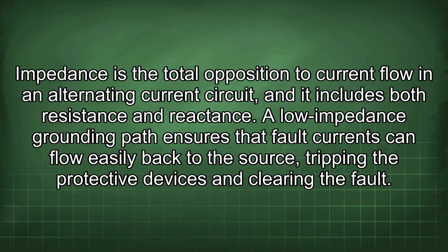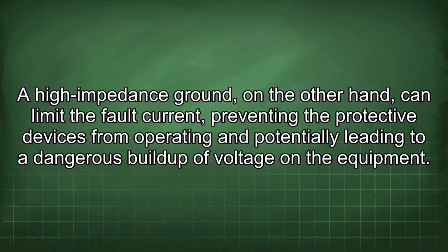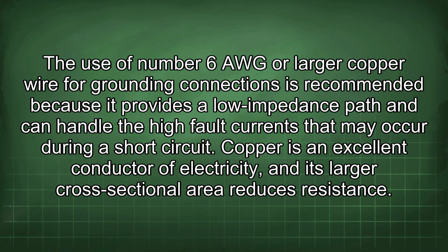A low impedance grounding path ensures that fault currents can flow easily back to the source, tripping the protective devices and clearing the fault. A high impedance ground, on the other hand, can limit the fault current, preventing the protective devices from operating and potentially leading to a dangerous buildup of voltage on the equipment. The use of number 6 AWG or larger copper wire for grounding connections is recommended because it provides a low impedance path and can handle the high fault currents that may occur during a short circuit. Copper is an excellent conductor of electricity, and its larger cross-sectional area reduces resistance.